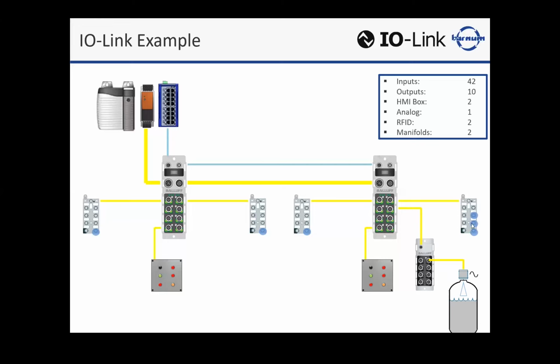more devices. Yeah, we said an analog card, a 2-point analog card in a PLC, was $650. Oh yeah. You'll see this Balluff analog block is somewhere in the neighborhood of $350. Wow. Giving you 8 points. That's quite a bit for flexibility. Huge savings.